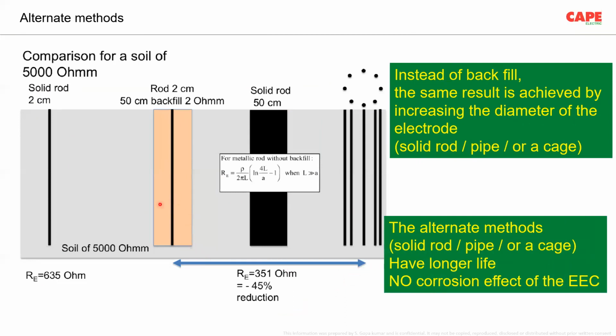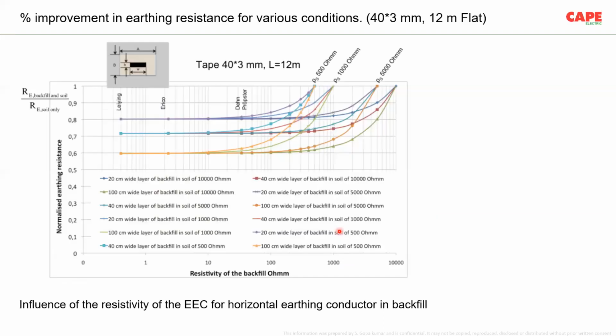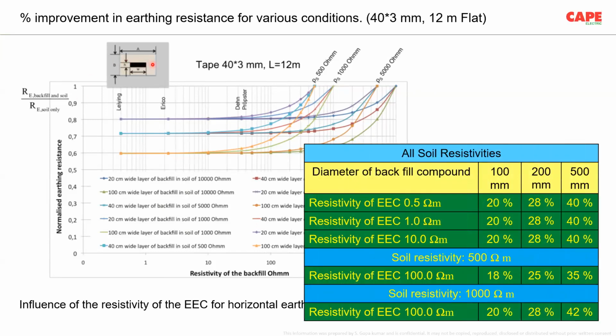Now, as an alternate to earth enhancing compound, these techniques also can be used. The advantage of these two techniques, a larger diameter solid pipe or a cage, is that earth enhancing compound actually increases the corrosion of your electrode, whereas with these two, the corrosion is influenced only by the soil, not by the earth enhancing compound, because earth enhancing compound actually accelerates the corrosion due to its low resistivity. So in these two cases, practically you can have a longer life because the corrosion is immaterial. The same paper which I will put up is a research paper, an internationally vetted paper. The same paper also explains a horizontal conductor.